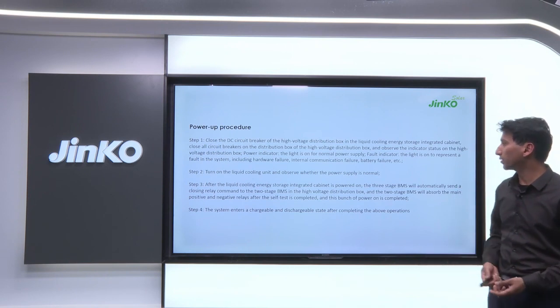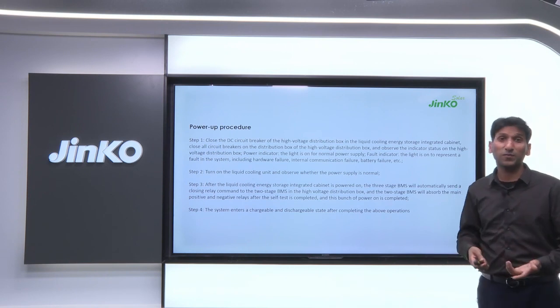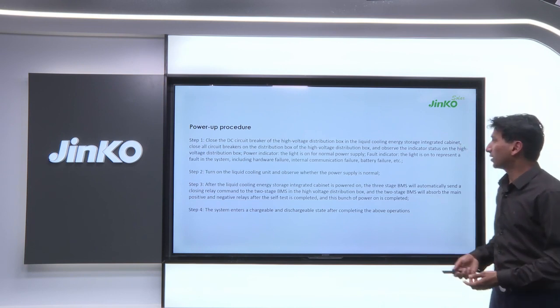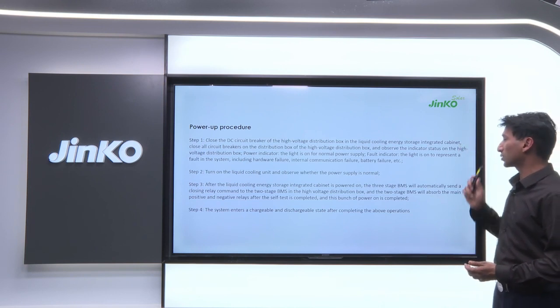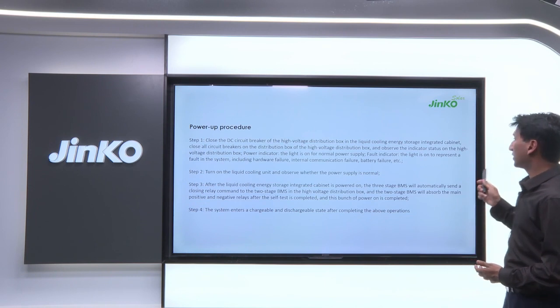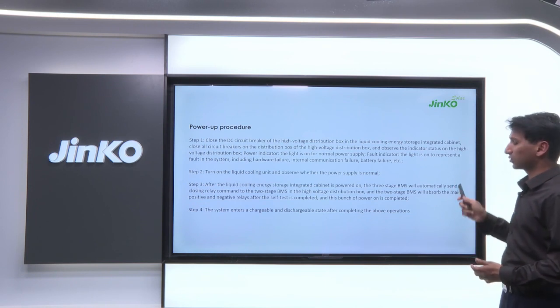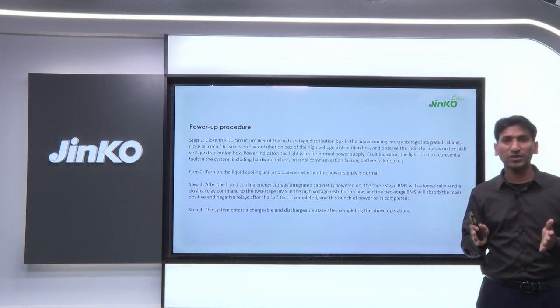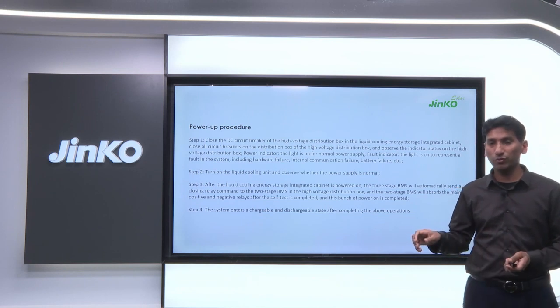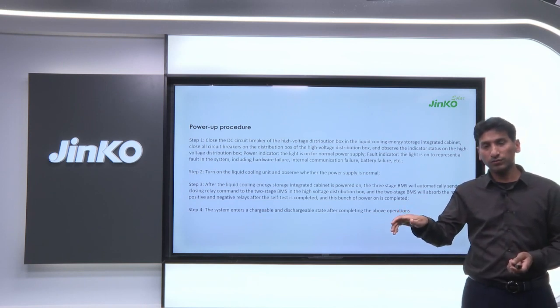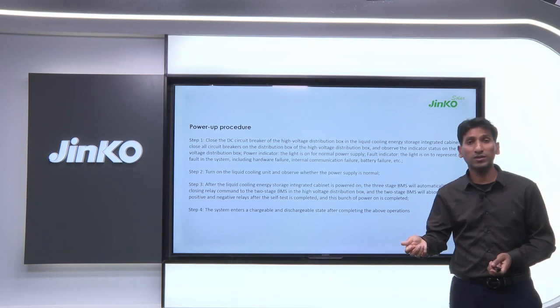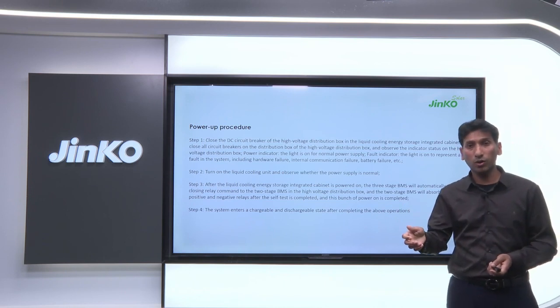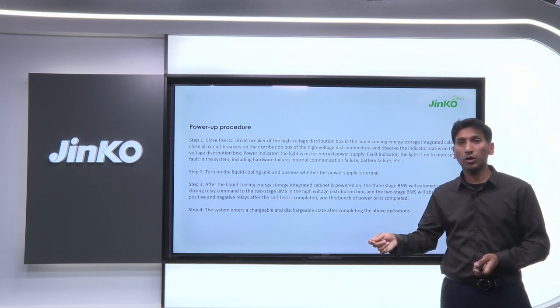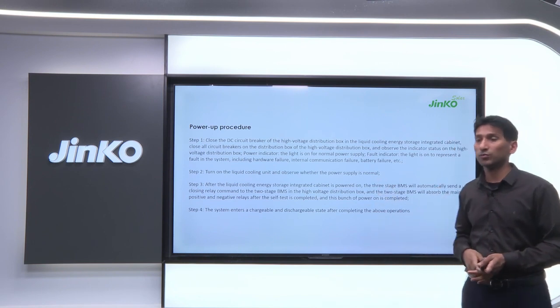Powering up the system is very simple. It's not very difficult, unless some fault happens. Power up procedure: you close the DC circuit breaker on the high voltage distribution box, and you close all circuit breakers in the distribution box. There are so many circuit breakers in the DC box. What you need to do is switch on the DC switch, the DC disconnector on the high voltage box. Then you switch on all the MCBs on the high voltage box.